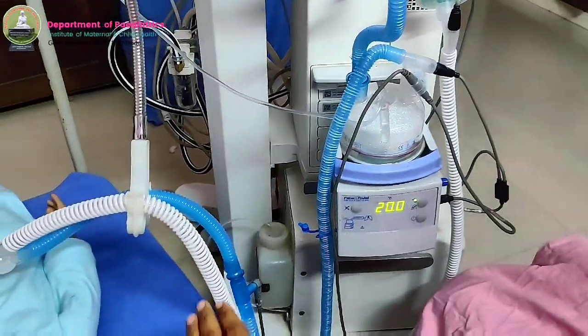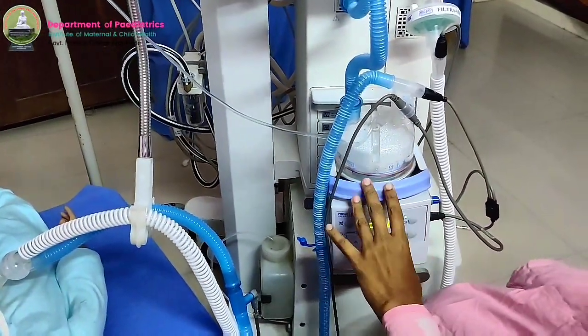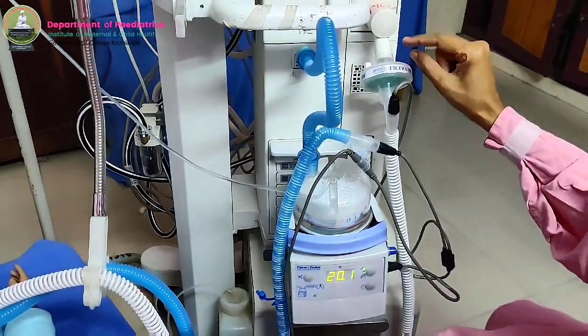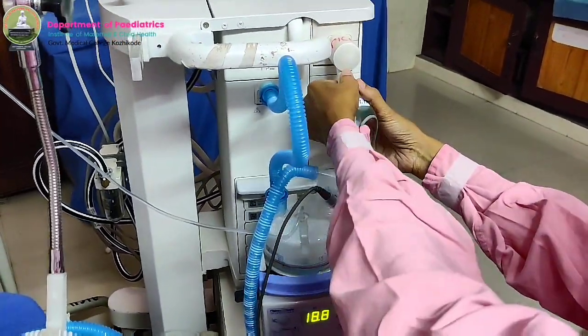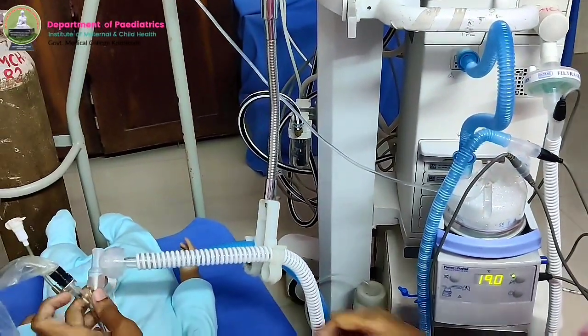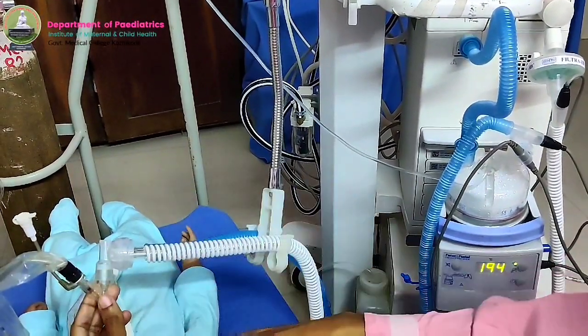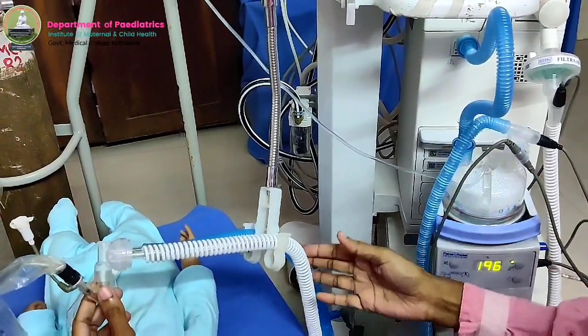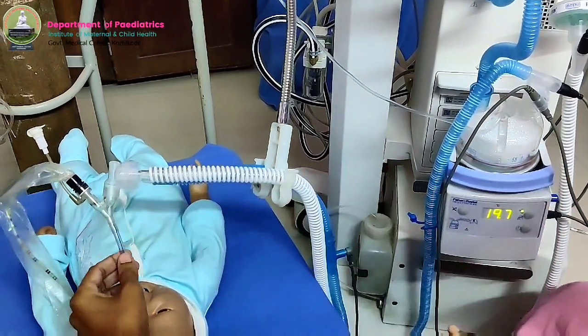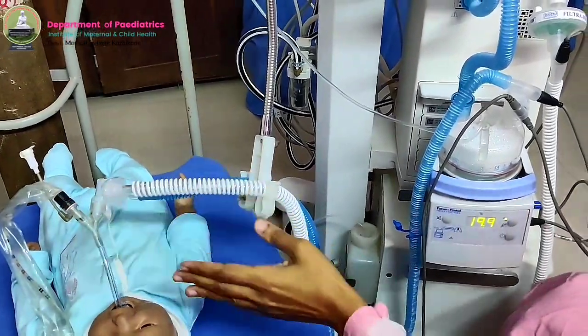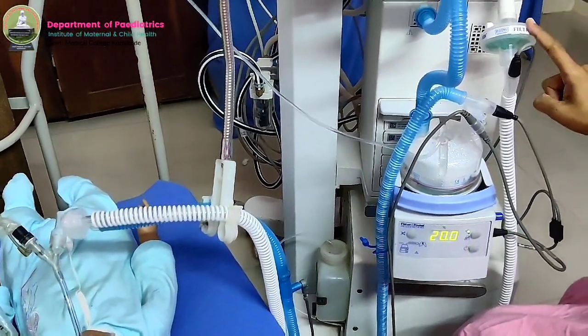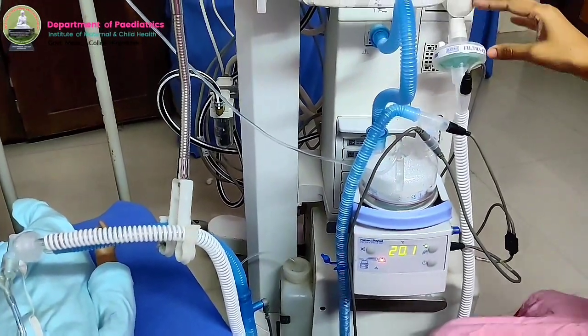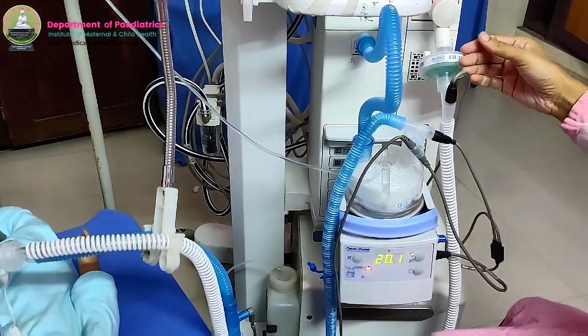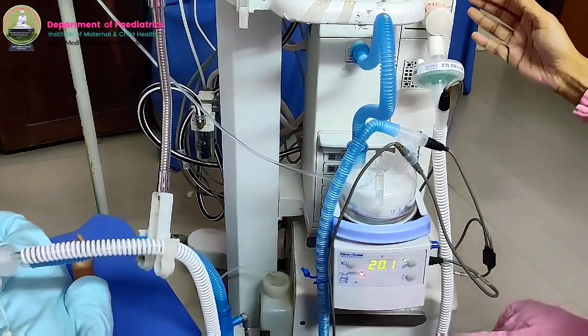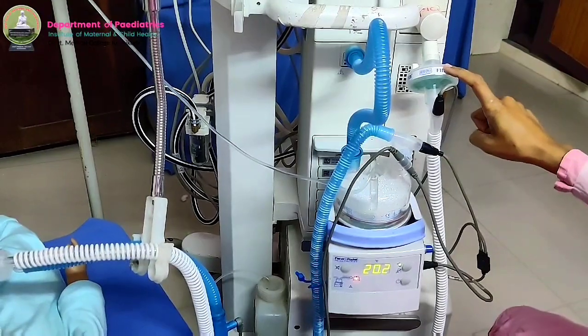Then if you are using a humidifier with the circuit, you are not supposed to keep this heat moisture exchanger with the patient end. If you keep an HME here, that will get wetted up very easily by the vapor produced from the humidifier chamber and the ventilation will get obstructed. So better to keep the HME at the expiratory end near the expiratory cassette. This is to prevent the infected aerosols being released into the atmosphere as such. So this acts as a virus filter, especially in a COVID patient.